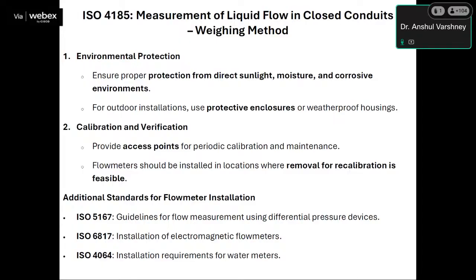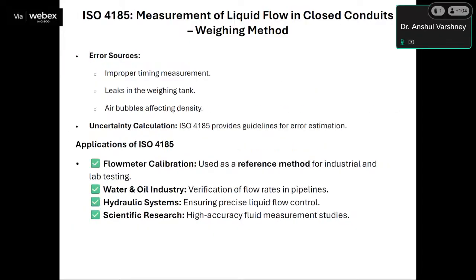So these are the basic guidelines provided in ISO 4185 for calibration of flow meters for measurement of liquid flow in closed conduits. And there are some additional standards for flow meter installation, like ISO 5167, which provides guidelines for flow measurement using differential pressure devices like orifice and venturi flow meters. ISO 6817 provides installation of electromagnetic flow meters.